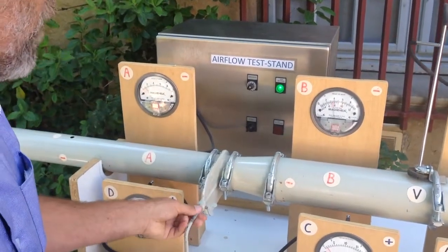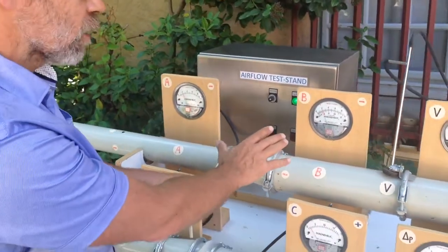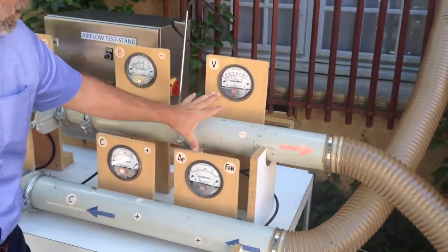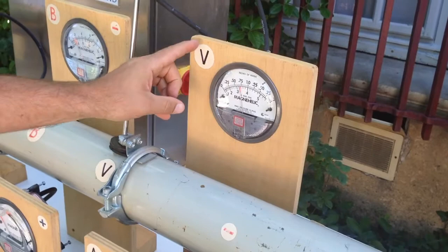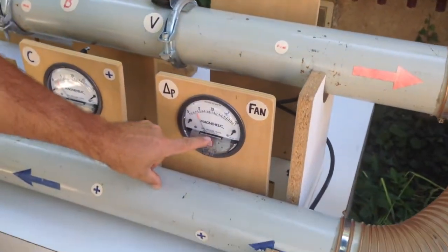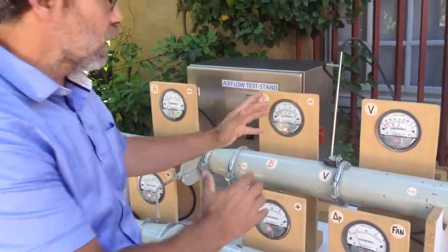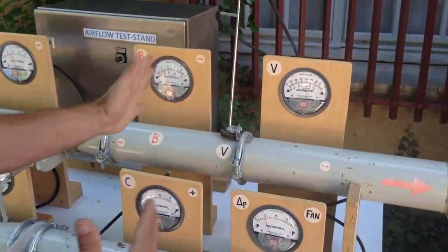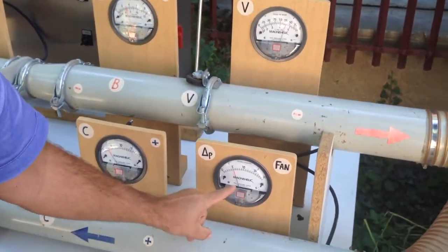Now, what's very important, at the same time we do this, so I go back to base condition, and now I watch what the fan is doing. This is the airspeed in the duct, and that's the differential pressure created by the fan. You remember well, when we're speeding up the fan, both of these go up. Let me do it one more time. When I speed up the fan, the airflow goes up and the static pressure goes up.